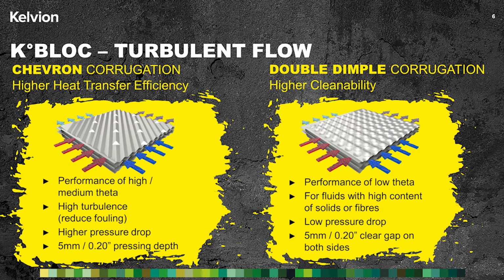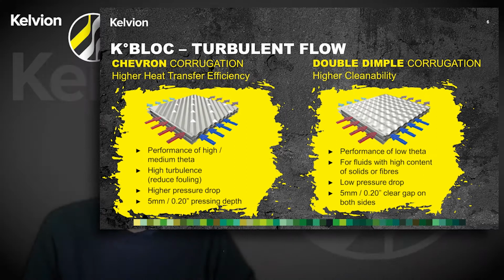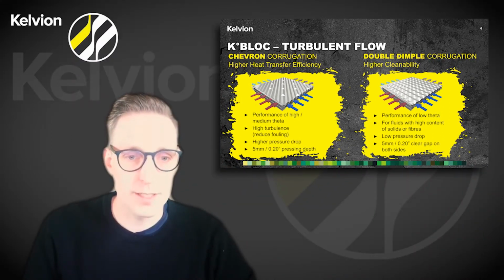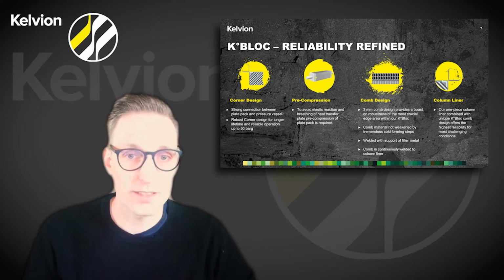The second corrugation type is the double dimple. It performs with slightly lower heat transfer coefficients but is capable of handling solids and small fibers. Also, where only small pressure drops are permissible, such as small vacuum condensers for instance, the double dimple offers advantages over other corrugation types. And an even easier cleanability because of the continuous gap is an additional pro for the double dimple corrugation.